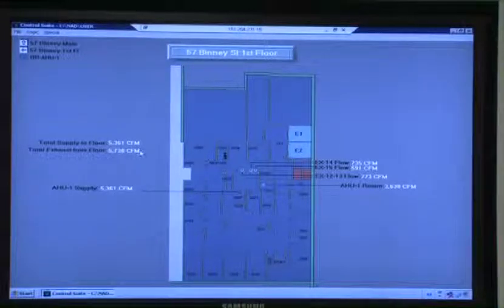It's telling me that floor is negative, which I have to go back to the balances and all that stuff to figure out, because no floor's got to be negative. They all have to be neutral or positive floors. Go ahead. Are you just questioning that reading? The balancer is going through and confirming all of the flow stations, so some of these numbers might need to be adjusted as far as what he's reading after each traverse of the duct.